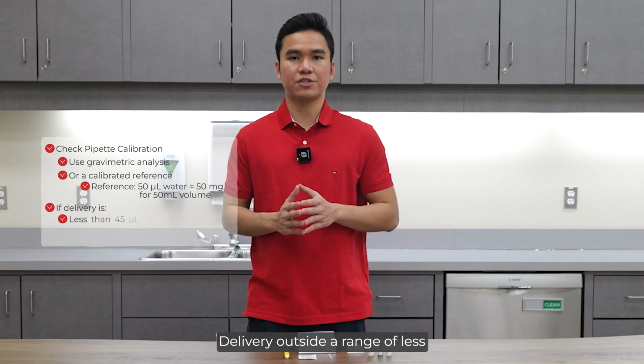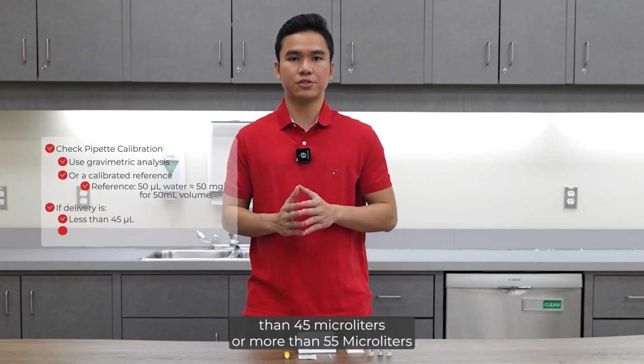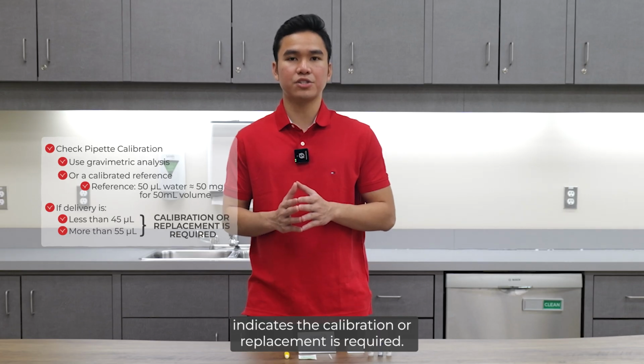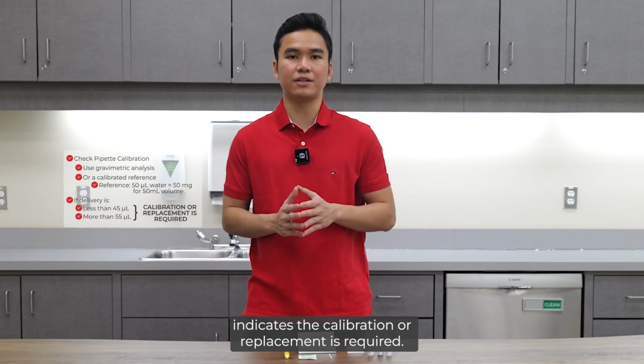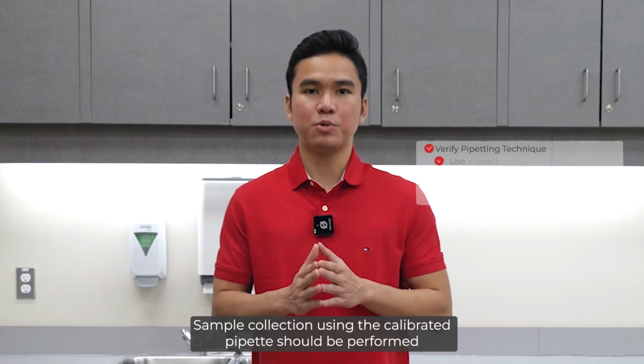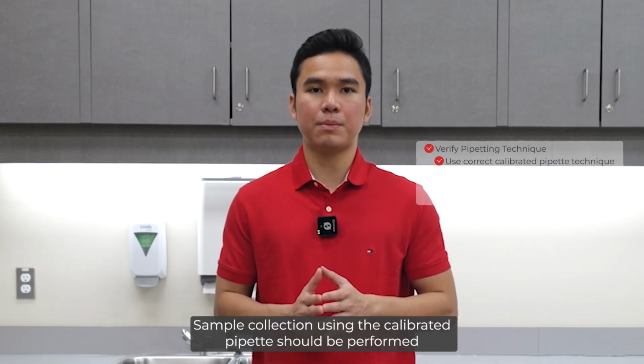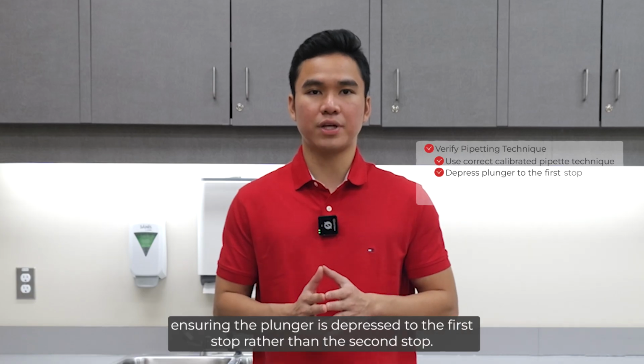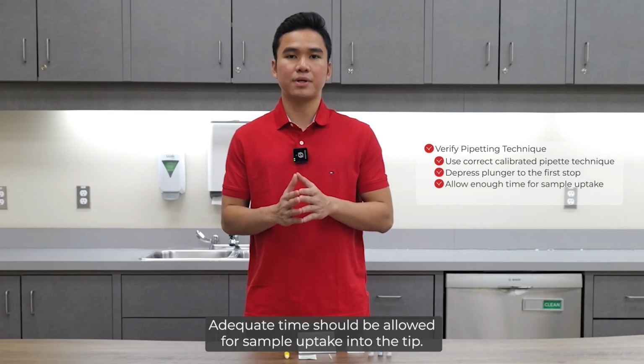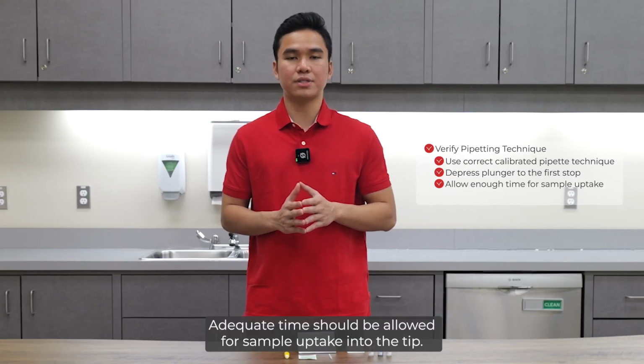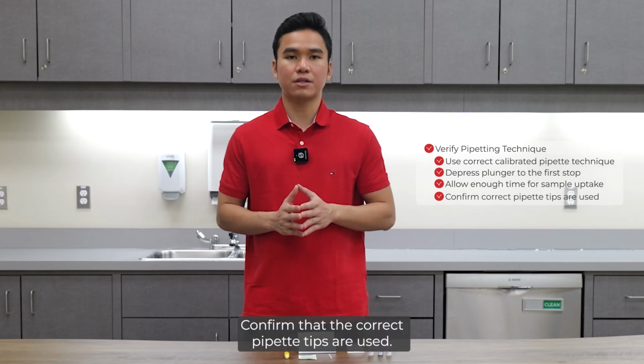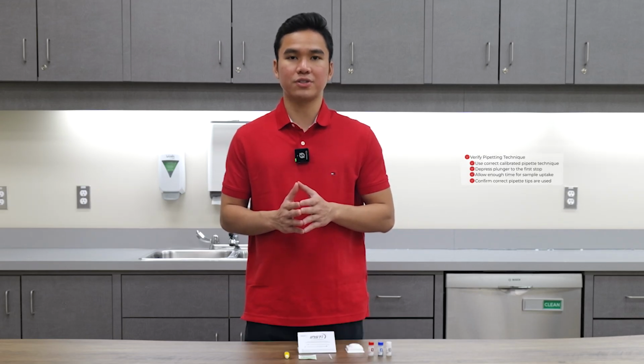Delivery outside a range of less than 45 microliters or more than 55 microliters indicates that calibration or replacement is required. Also verify pipetting technique. Sample collection using the calibrated pipette should be performed, ensuring the plunger is depressed to the first stop rather than the second stop. Adequate time should be allowed for sample uptake into the tip. Confirm that the correct pipette tips are used.